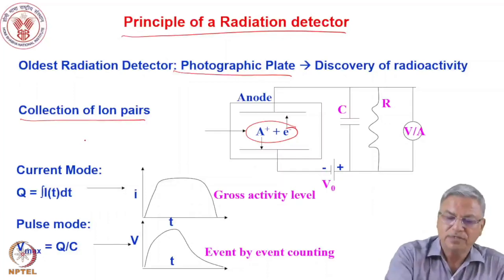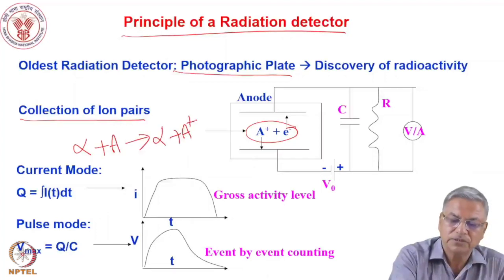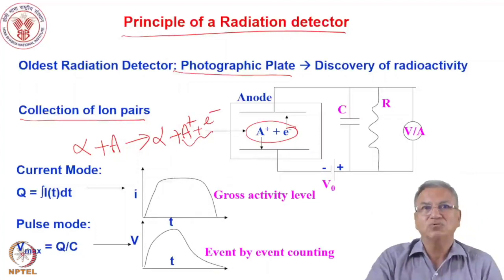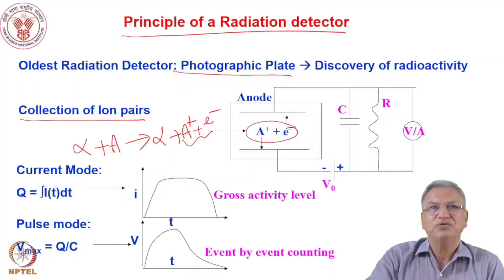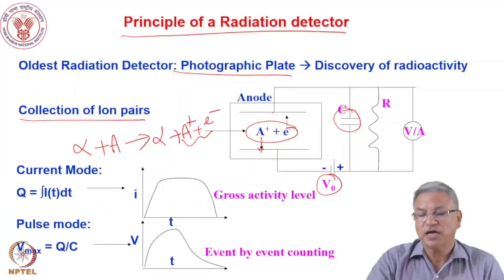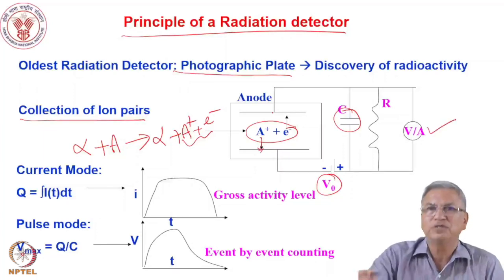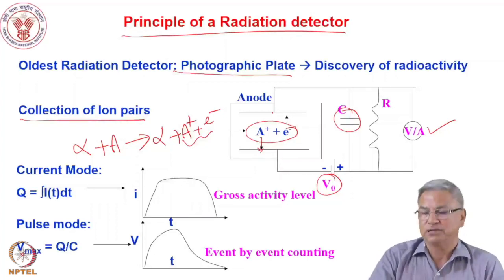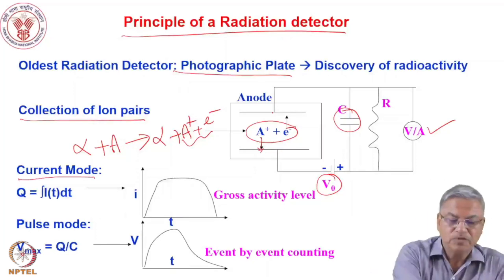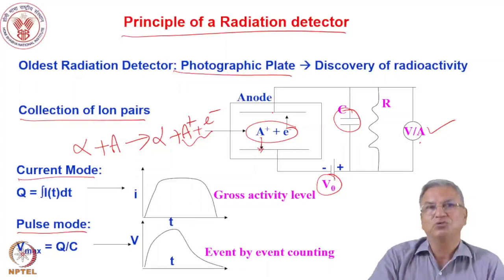The net result of all types of interactions of ionizing radiation is the production of ion pairs. Suppose an alpha particle interacts with atom A: the alpha plus A gives an ionized atom and a free electron. If you collect this electron and positive ion at their respective electrodes, you can collect the signal. Electrons are collected at the anode and positive ions at the cathode by applying a potential, essentially charging a capacitor, which discharges through a load resistance R. That discharge can be measured as a voltage or a current. We will discuss both mechanisms and their merits and demerits.